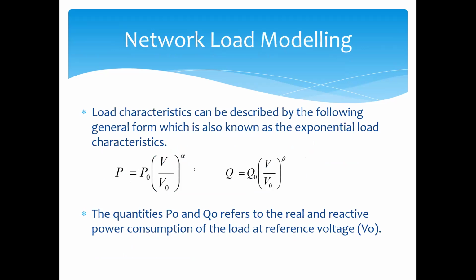Load characteristic can be described by the following general form, which is known as the exponential load characteristic. Here, P is the power consumption at present, and P naught is the power consumption at the reference voltage V naught, and V is the present voltage. Q is the reactive power consumption at present, and Q naught is the reactive power consumption at reference voltage V naught. Alpha and beta are the coefficients for voltage dependence.